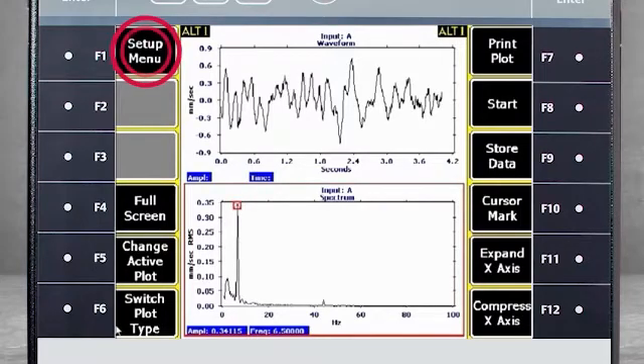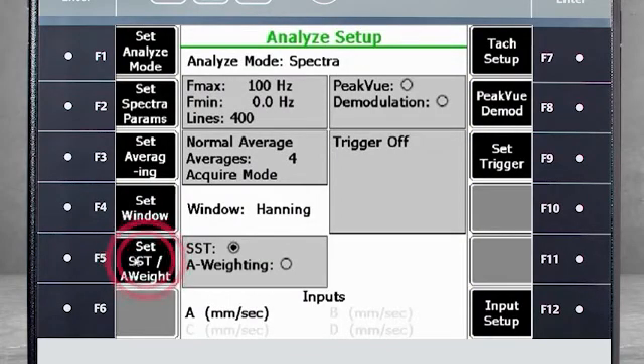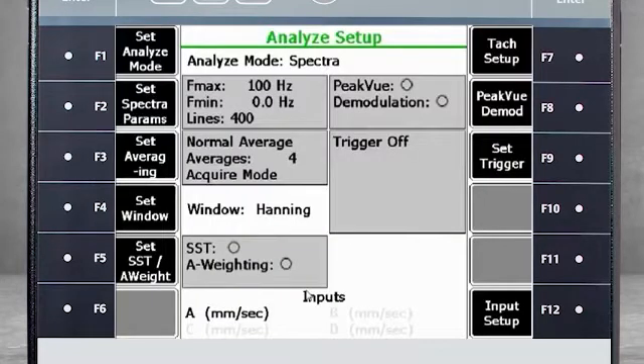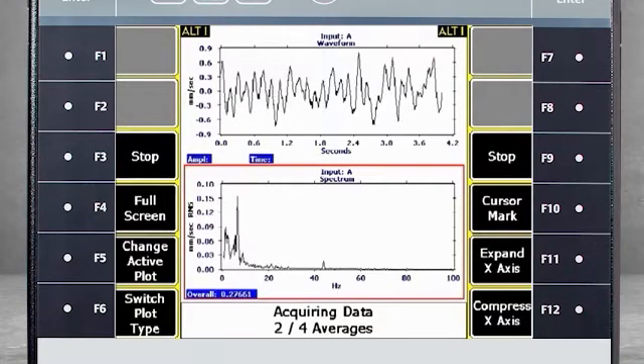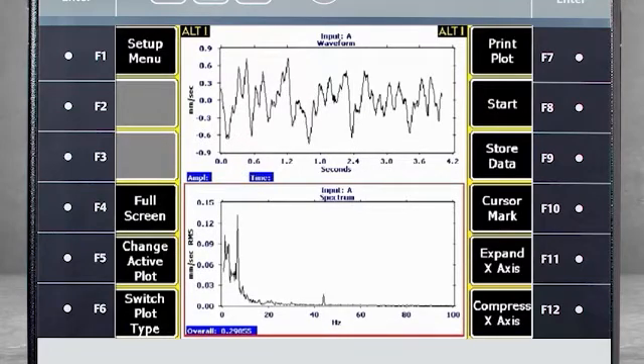Select F1 Setup menu — here you see that SST is enabled. Use F5 to disable SST and recapture the data. You can see in the low-frequency range that the noise floor is much higher now.